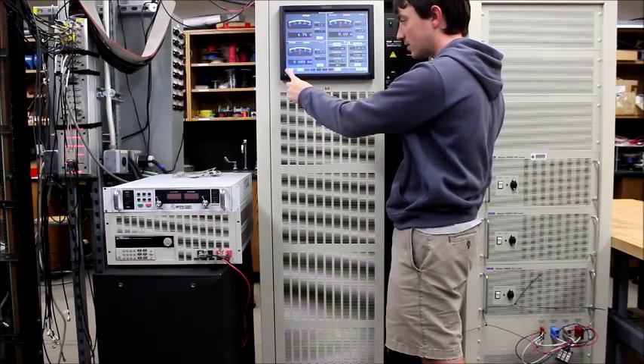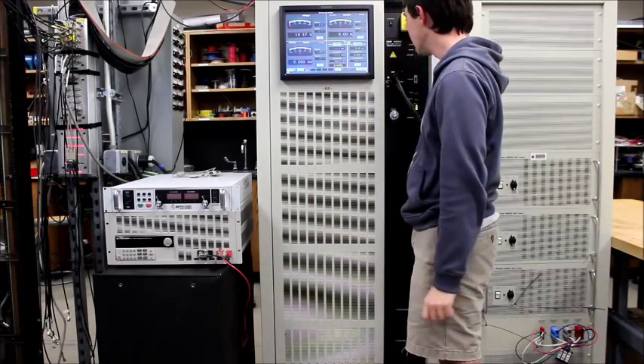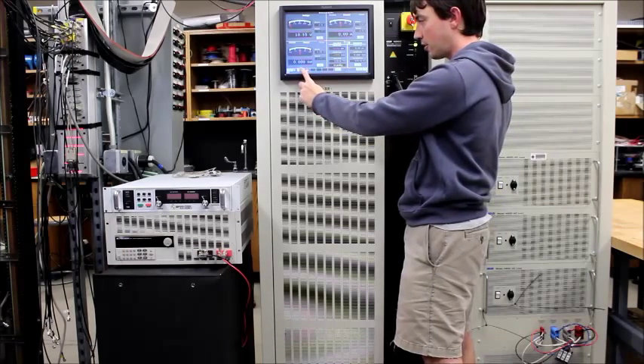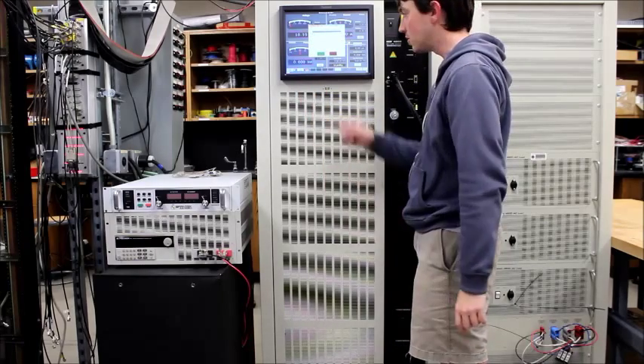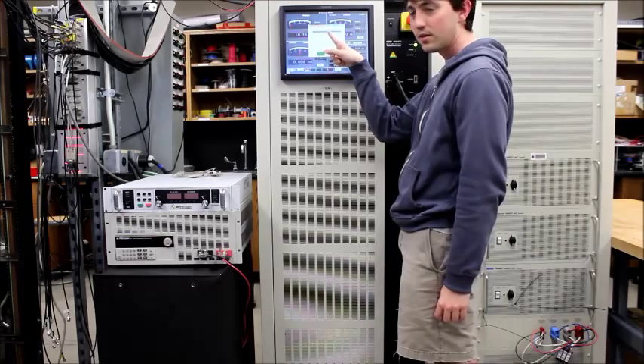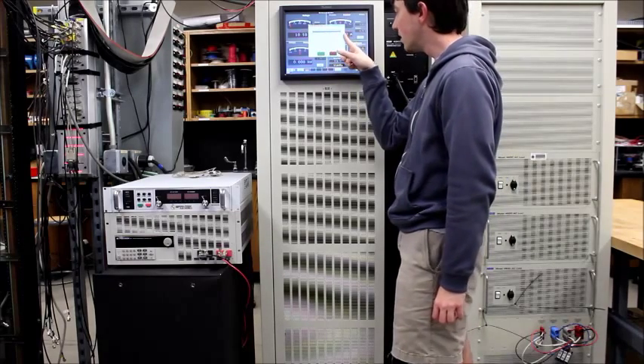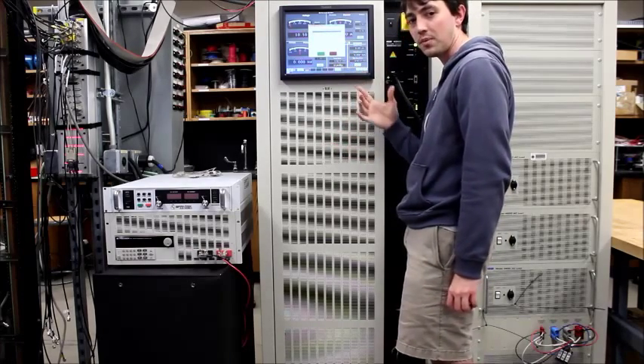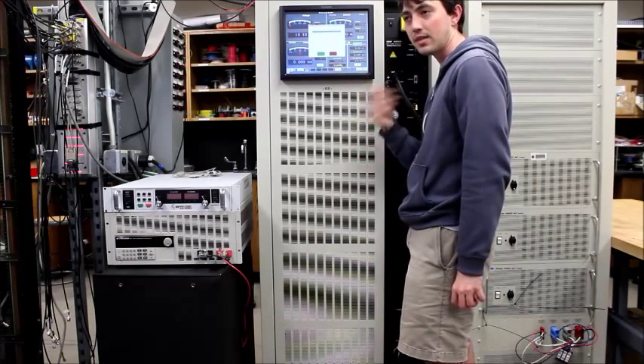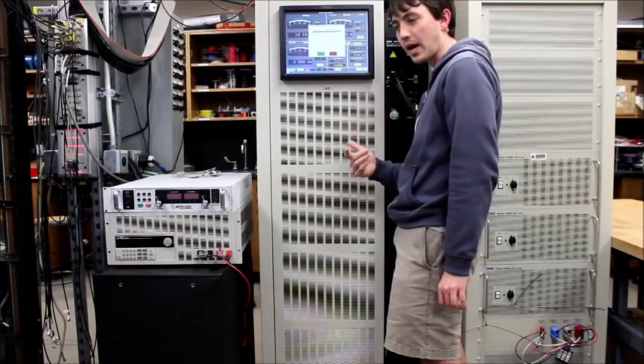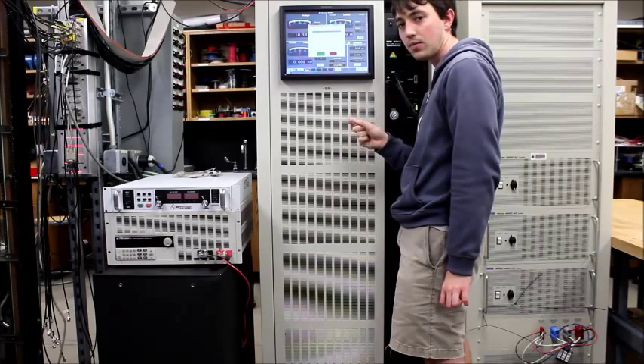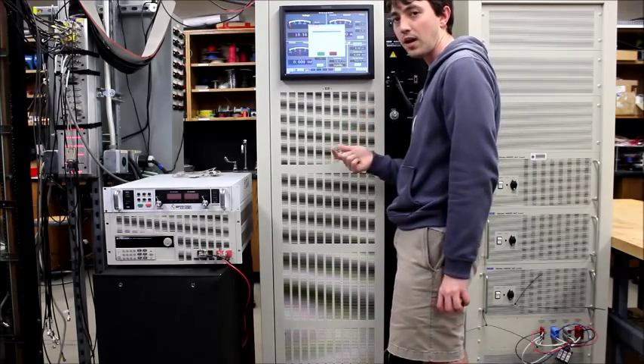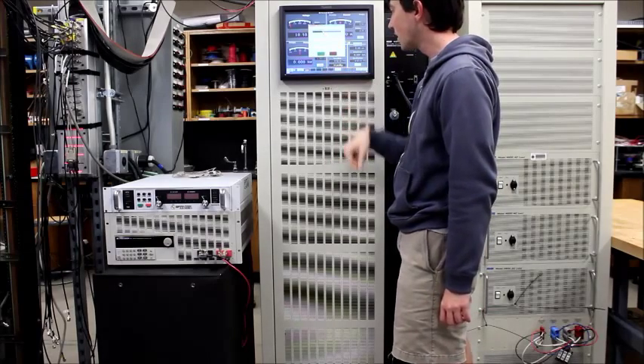So the next thing we can do is click on on/off, and now it's in standby. And then you can push on settings. And you have a couple options: you have standby, charge, discharge, and battery. Charge is going to present a voltage supply. Discharge is going to be a sink. Battery is going to be a sink or a source with an internal battery model with a series resistance. So for this one, we just want to make a DC supply, so we'll do the charge.